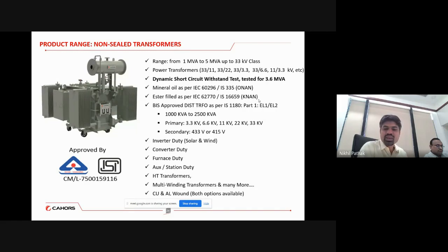Along with that, we are also encouraging both types of conductors, whether it is copper or aluminum, because globally, we being a global supplier, we have more exposure in aluminum wound transformers also, because in Europe, the cables are normally used with copper, and the transformers are used with the aluminum conductor. So we have more strength in terms of manufacturing and design to handle the aluminum conductor. In India, largely the distribution sector is using the copper conductor, and the renewable sector in India is more into aluminum use. So we have experience in both conductors in terms of transformer offering. So this product line we are offering is type tested and well established in India.